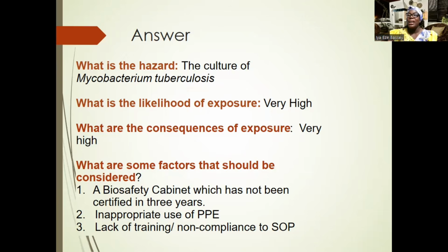So what factors did I look at to make this decision? Did I just wake up and say, no, tuberculosis is high? No. Number one, that biosafety cabinet that he's using has not been certified for 3 years. You don't even know whether that biosafety cabinet is working. In fact, it may work in such a way that it is working to infect you. Your biosafety cabinet has to be regularly certified, and then the kind of personal protective equipment he is using is not the correct type.